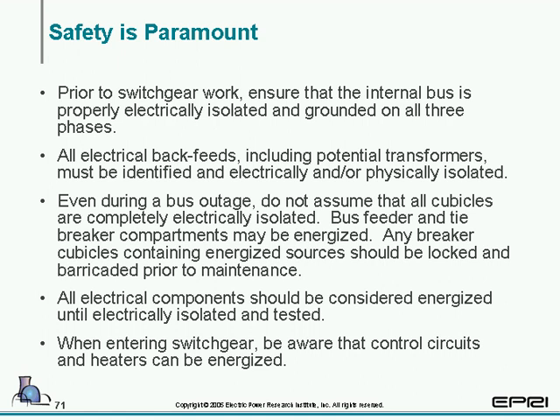Prior to switchgear work, ensure that the internal bus is properly electrically isolated and grounded on all three phases. All electrical backfeeds, including potential transformers, must be identified and electrically and/or physically isolated. During a bus outage, do not assume that all cubicles are completely electrically isolated, even during a bus outage. Bus feeder and tiebreaker compartments may be energized. Any breaker cubicles containing energized sources should be locked and or barricaded prior to maintenance. Components should be considered energized until electrically isolated and tested, very critical.